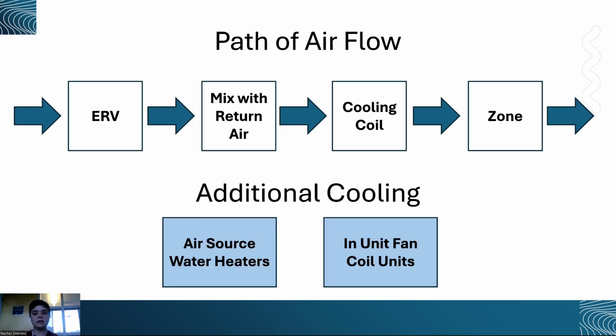So for our final design, here we have a path of the airflow as it goes through the building. Entering air starts by entering through the ERV, exchanges with that exiting air and dehumidifies. It then mixes with the return air. We didn't want to use a dedicated outdoor air system just because we wanted to utilize the air that had already been cooled and dehumidified. We then go to the cooling coil, which removes that humidity and cools it even further, and it's applied to the zone. We do have additional cooling within the zone. We have the air source hot water heaters that should take about 1 kilowatt of heating out of that cooling demand. And then we also have in-unit fan coil units as needed.